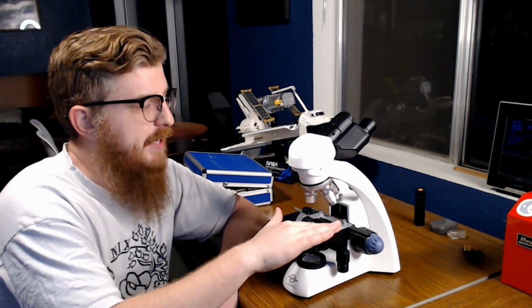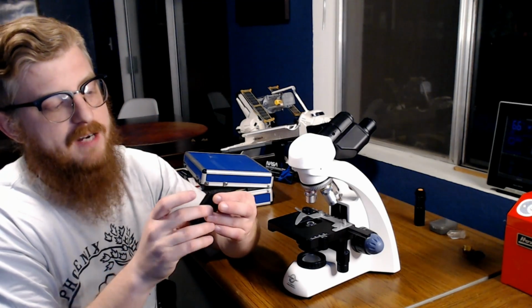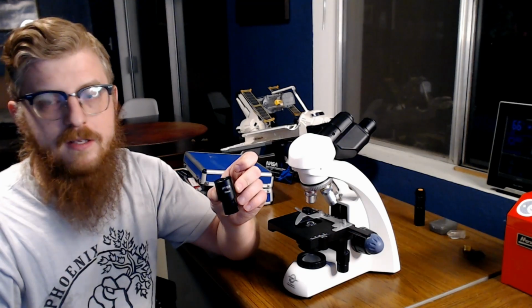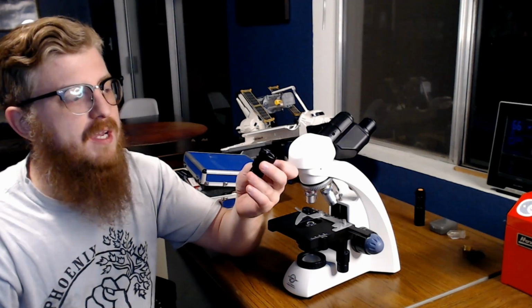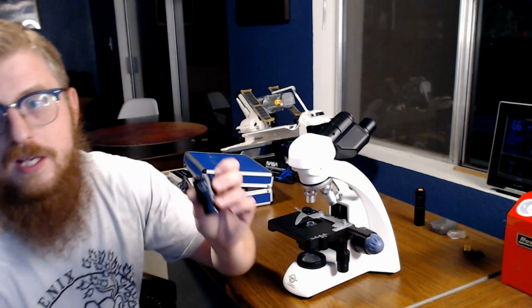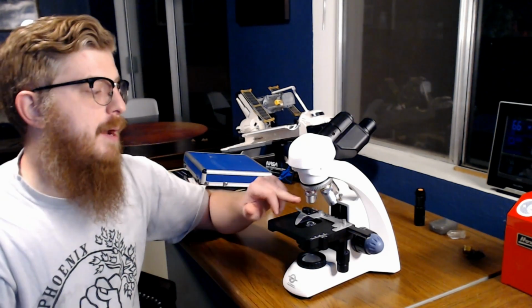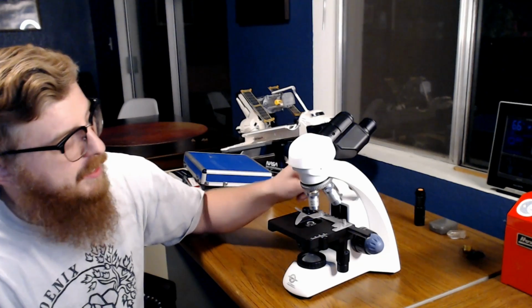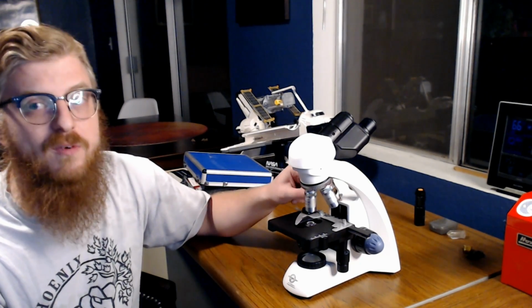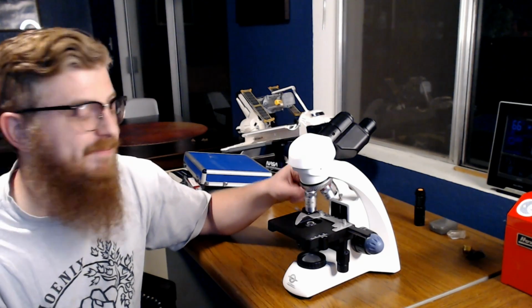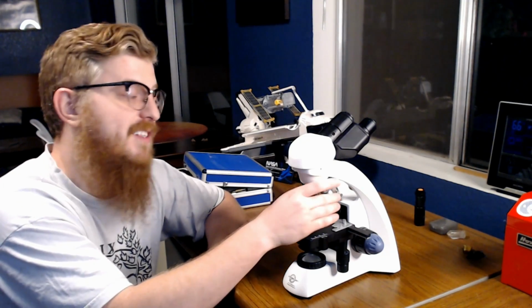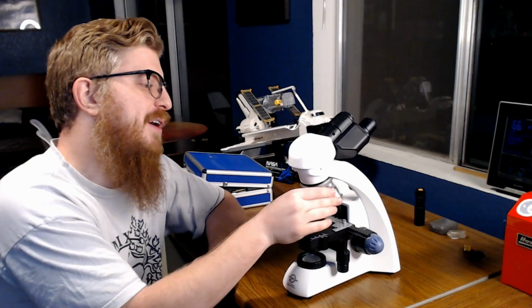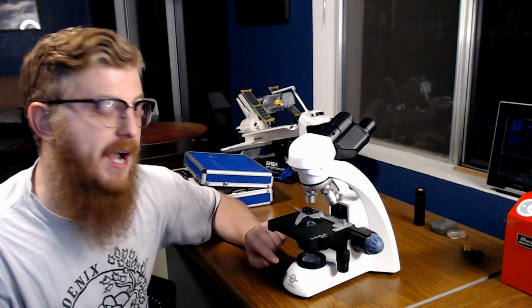All right, and basically the way the magnification works, the eyepiece itself has a base magnification. So this is an 18 millimeter eyepiece. This is a nice wide field of view eyepiece. It is a 10x magnification. So we take the eyepiece magnification, we multiply that by the objective lens magnification. So 10 times 4 is 40. 10 times 10 is 100. 10 times 40 is 400. 10 times 100 is 1,000. So with these particular eyepieces, we can get up to 1,000 times magnification, which is pretty darn good for a relatively inexpensive microscope. Again, this is a Micro Explorer CM1 compound biological microscope.